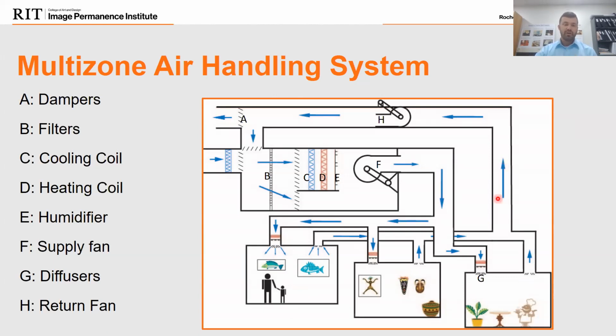So I'm trying to achieve 70 degrees here, maybe 60 degrees here, and maybe 72 here. So I have to return all this air back to the unit and then cool it down to the coldest condition. So now I have to cool it down to 60 degrees to satisfy this room. And then as the air goes out, I'm going to heat it to, again, 70, 60. I'm not going to heat it because I'm at 60, and then I heat it to 72 to bring it back and do it again. So I'm doing multiple conditions. I'm using a lot of energy to achieve that.